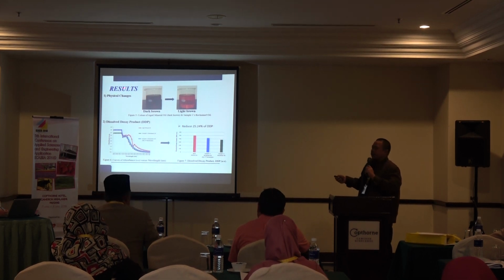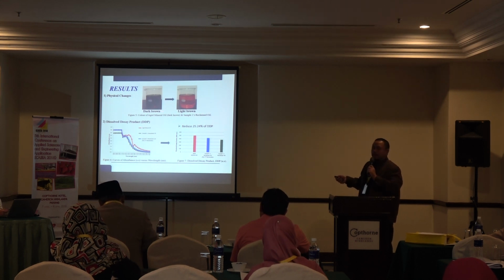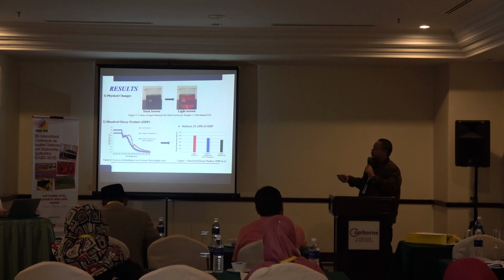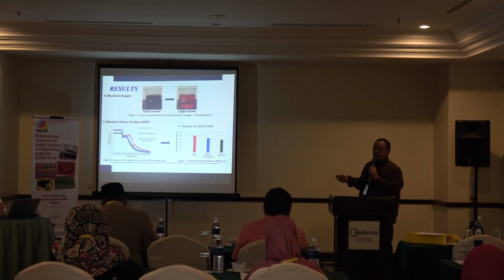The in-service oil itself is dark brown, which means the oil has aged in service. Then we do the reclamation process. If it turns light brown, it means the fuller earth has shown what we call good practice, that it has reclaimed or recycled the oil. But we need to extend this work and do another cycle, because here we applied only one cycle of the reclamation process. If we do a lot of cycles, we can make the transformer oil lighter and brighter.